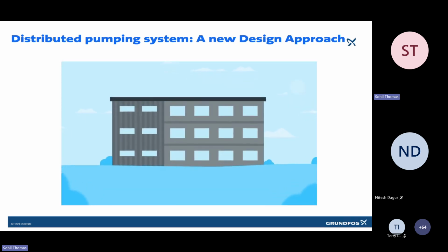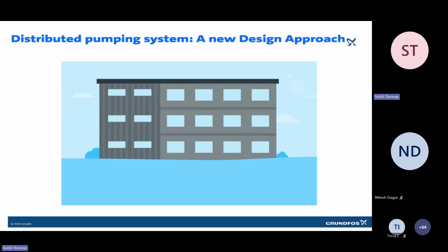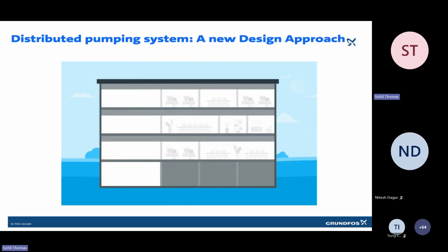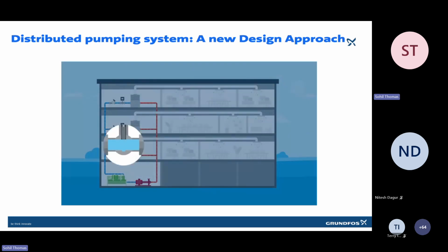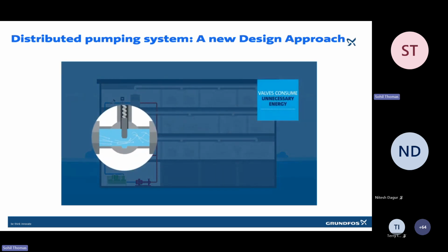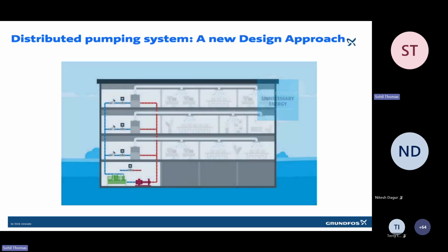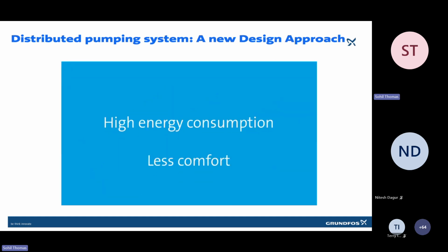There are many considerations when designing a cooling system for commercial buildings. To cool a building, existing chilled water systems generally use large centralized pumps and chillers in the mechanical room for pushing water around the chilled water loops. Regulating the flow due to the varying cooling needs is traditionally done using balancing and control valves, typically located close to the terminal units. But even efficient valves consume unnecessary energy due to pressure losses. Furthermore, a bypass line is typically used in the system to ensure sufficient flow to the chillers. Cooling systems with central pumps and valves have been designed in this way for decades. However, there are issues shared by existing cooling systems that lead to high energy consumption and less comfort in the building.